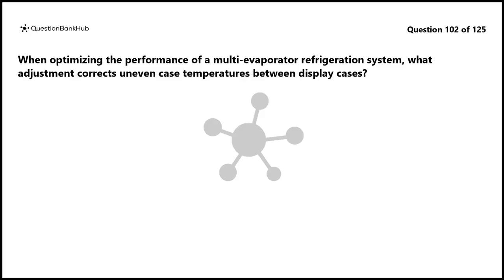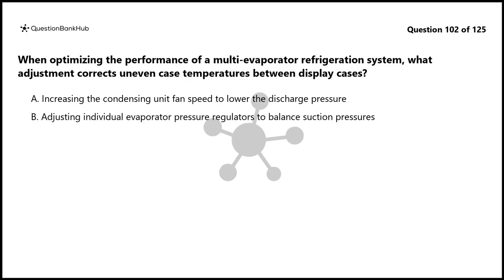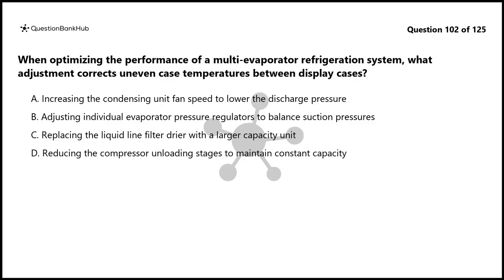Question 102. When optimizing the performance of a multi-evaporator refrigeration system, what adjustment corrects uneven case temperatures between display cases? A. Increasing the condensing unit fan speed to lower the discharge pressure. B. Adjusting individual evaporator pressure regulators to balance suction pressures. C. Replacing the liquid line filter dryer with a larger capacity unit. D. Reducing the compressor unloading stages to maintain constant capacity.